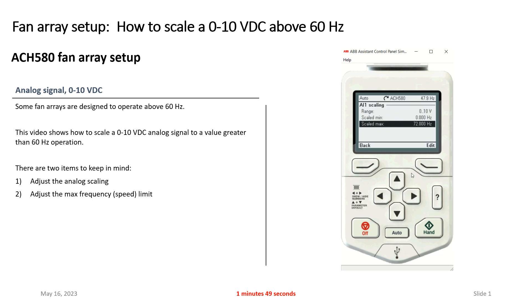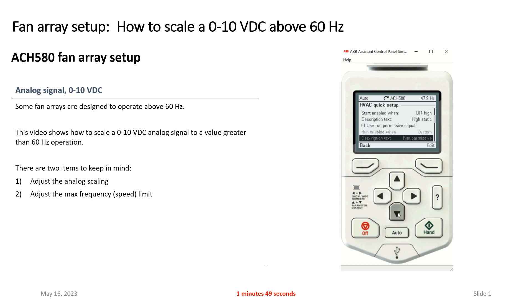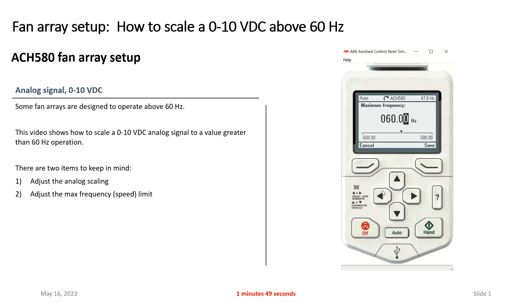And there you go. Now you probably think I'm done — 0 to 10 volts equals 0 to 72 hertz. Well, I'm half done. What I just took care of right there is the scaling from the automation system to the drive, to make sure the drive knew what it was supposed to do based on the analog signal coming in. However, drives also have limits in them. A typical factory default on a drive is going to be 60 hertz limit here in the US. You see this maximum frequency: 60 hertz. So now I need to change that limit on my maximum frequency to also be 72 hertz.